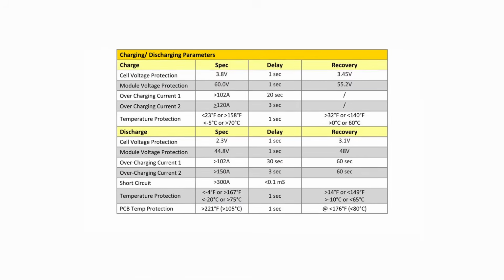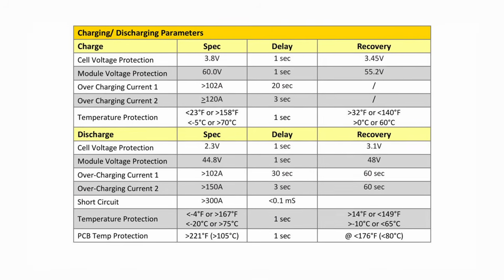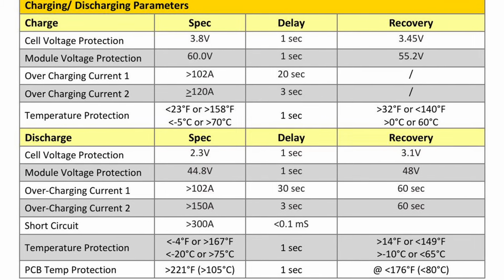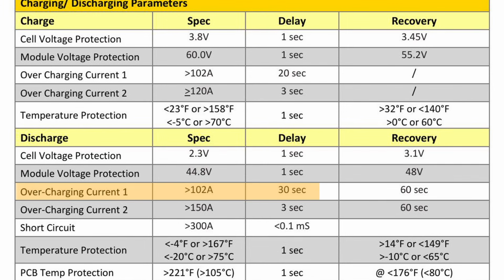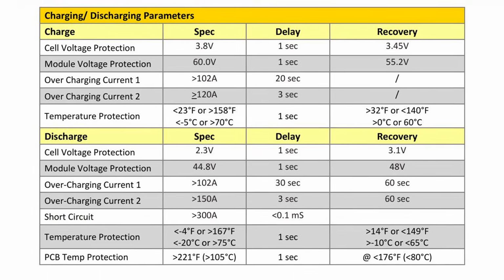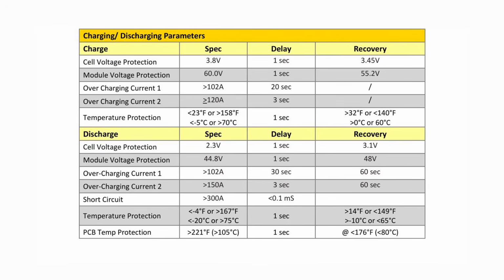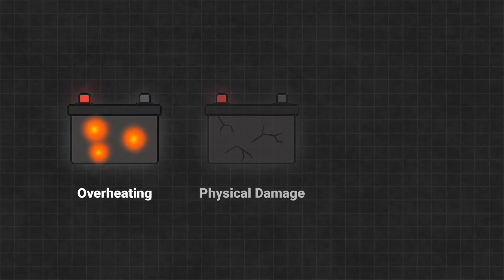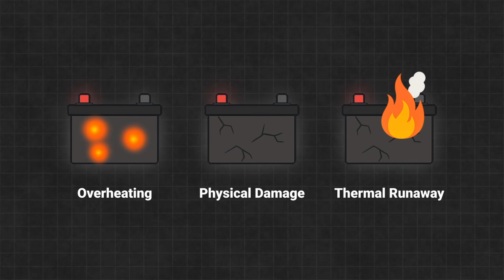For example, for this EG4 48 volt 100 amp hour battery, the datasheet specifies that if the current is between 102 and 150 amps, the BMS will shut it down in 30 seconds. If the current is between 150 and 300 amps, the BMS shuts down in 3 seconds, and if the current exceeds 300 amps, the BMS reacts in under 0.1 milliseconds. These overcurrent protection measures aren't there to prevent capacity loss, they're there to prevent overheating, damage, or thermal runaway.